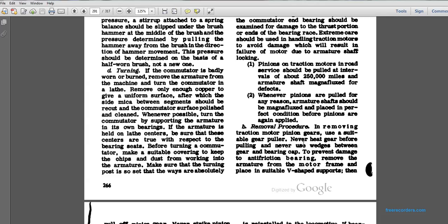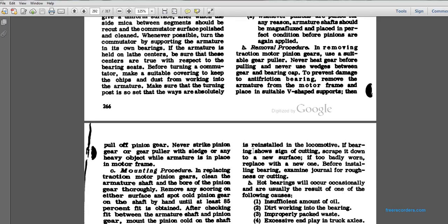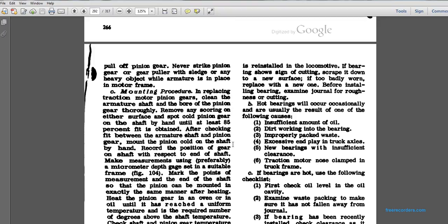Removal procedure. In removing traction motor pinion gears, use a suitable gear puller. Never heat a gear before pulling. Never use a wedge between the gear and bearing cap. To prevent damage to the anti-friction bearing, remove the armature from the motor frame and place it on suitable V-shaped supports. Then pull off the pinion gear. Never strike the pinion gear or gear puller with a sledge or a heavy object with the armature placed in the motor frame.